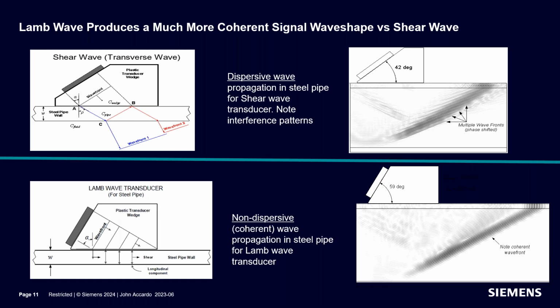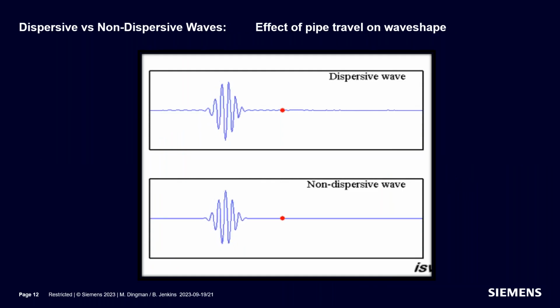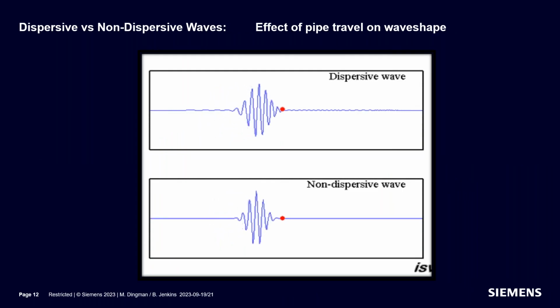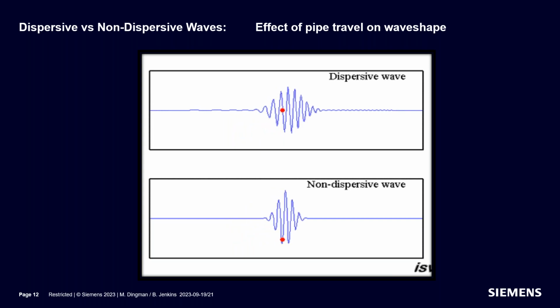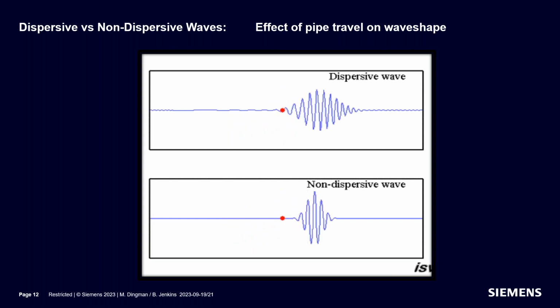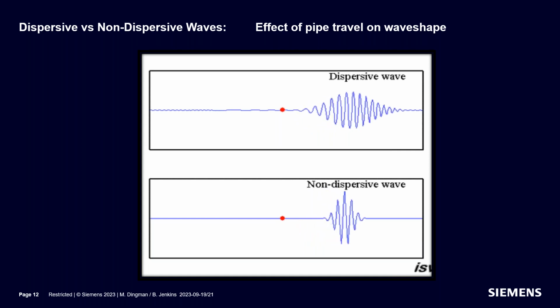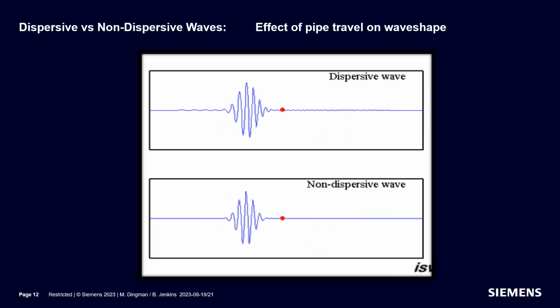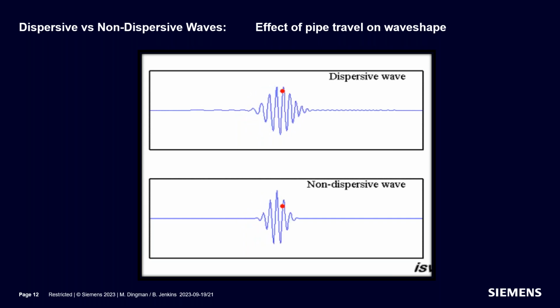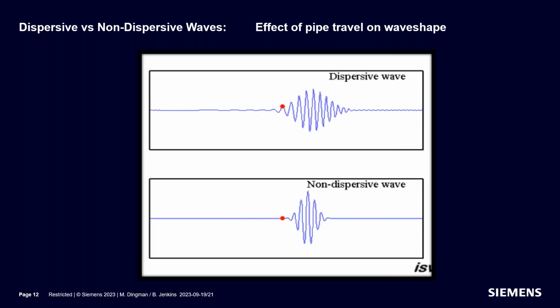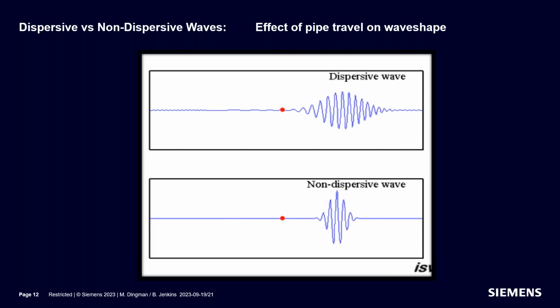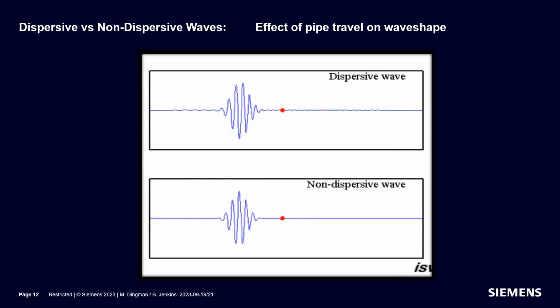So the key is ultimately the received signal quality and how it is affected by changes in the application, such as temperature, pressure, flow velocity, and fluid type. And we can see an example of that here. At the top, you see a dispersive wave, and as it travels down the pipe wall, it's changing. Whereas on the bottom is a Lamb wave, a non-dispersive wave. And as it travels, it stays exactly the same. So the wave that it's injecting into the pipe wall, regardless of where it's emerging from the pipe, is the same.